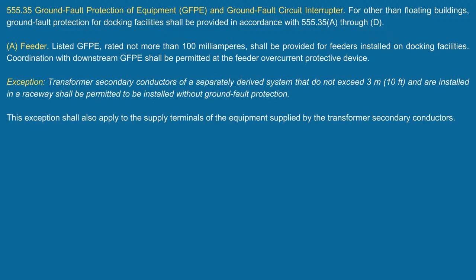Matter of fact, if you go look at Article 316, the very first word in there that deals with all your different boxes and everything, it says outlet. Oh, you're talking about 314. I mean 314, Article 314. I'm sorry. Yep. Now, let's look at the section, see what it says here. It says, for other than floating buildings, ground fault protection for docking facilities shall be provided in accordance with 555.35A through D. Okay? Yep.